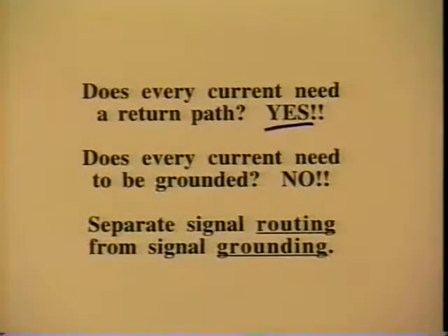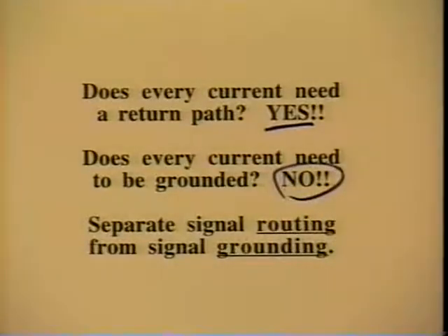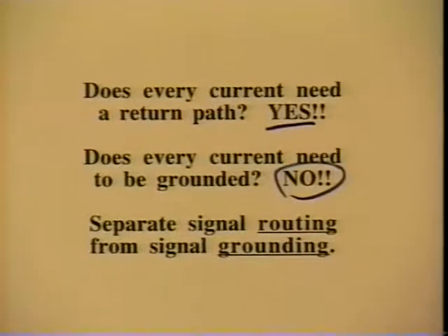Does every current need to be grounded? No, not all currents need to be grounded. Some do, some don't. When do they need to be grounded? When do they not need to be grounded? We just talked about some of that. Some currents need to be grounded to avoid susceptibility to ESD. Some currents need to be grounded so that the common mode voltage coming out on those wires is less for safety purposes. And then on the other hand, low frequency currents, we don't want to ground them too often because then we'll get into ground loop problems.